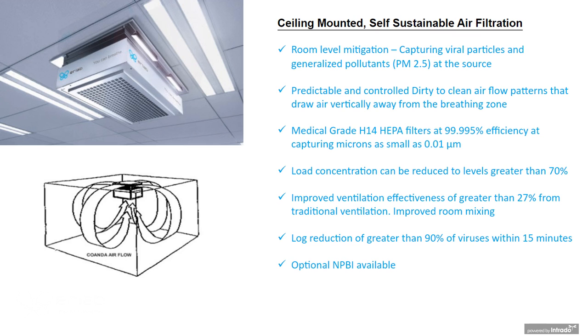Now, you remember further back I mentioned needlepoint bipolar ionization. It works if you have the proper dispersion. So these systems do have optional needlepoint bipolar ionization systems where it's installed within the cavity chamber between the filter and the fan. So we're constantly dispersing negatively and positively charged ions while we're filtering at the same time. This becomes extremely efficient.